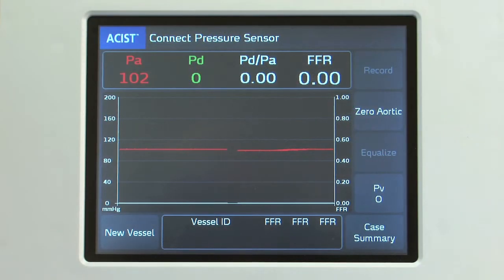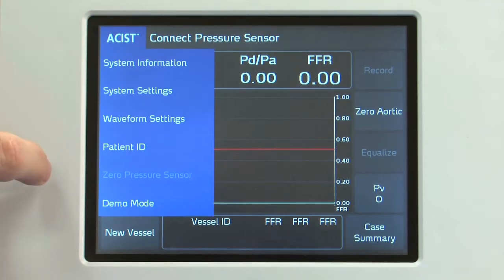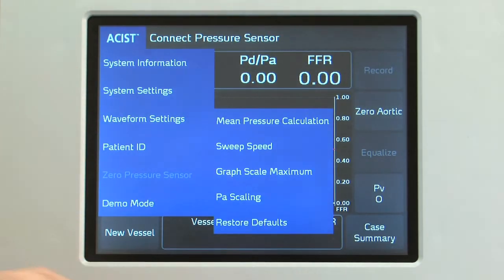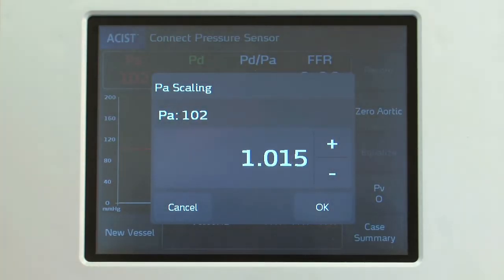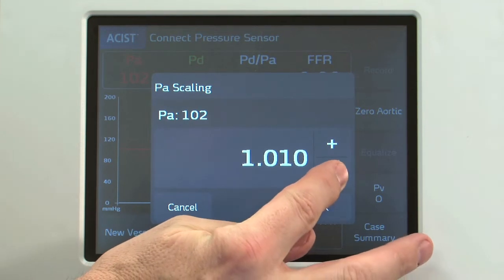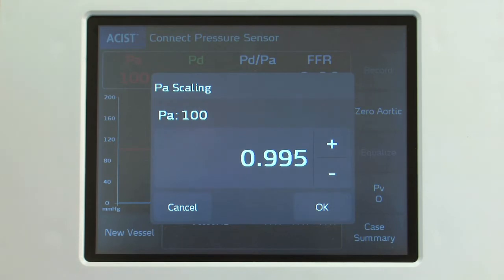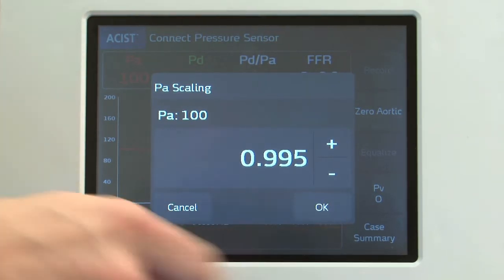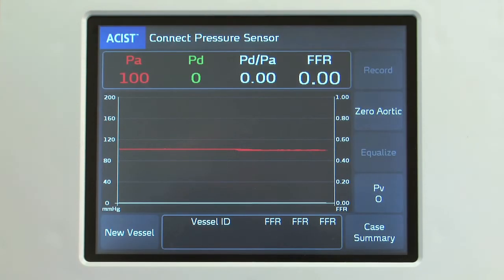PA scaling is used when we input a known pressure into the hemodynamic system. In this case, 100 millimeters of mercury pressure is input into the hemodynamic system, but the RXi is reading 102. We can adjust the PA measurement by going under the drop-down menu to Waveform Settings and PA Scaling. Now, by adjusting the PA scaling down, we can set this to 100 millimeters of mercury pressure, and hitting OK calibrates the Rxi Console.